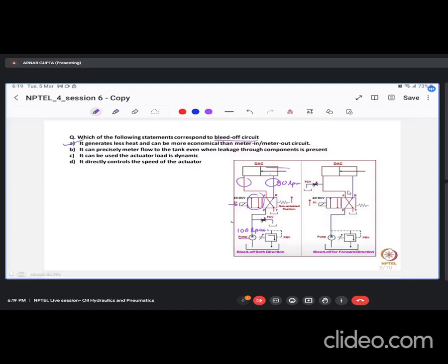From this flow control valve, there can be some leakage happening, and instead of the 10 liters per minute that I showed that bleeds off, it can be say around 12 liters per minute. This extra 2 lpm that I am writing is the leakage. So the remaining flow that goes into the circuit is basically 88 liters per minute.